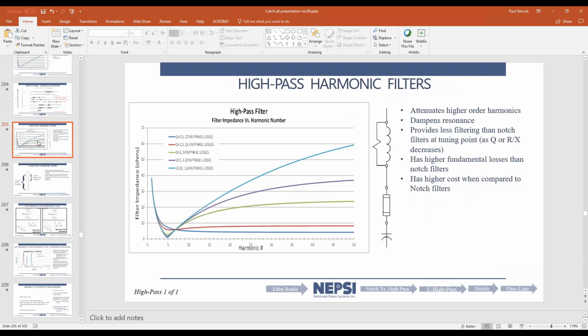And it's a damped harmonic filter is what you're looking to do to eliminate resonance concerns by harmonic filters themselves. And it's very common in very large copper concentrator plants that use cycloconverters, that these damped harmonic filters be used. Also common in the arc furnace world, where you have lots of harmonics at different frequencies. These types of filters are used, and notch filters are not used.